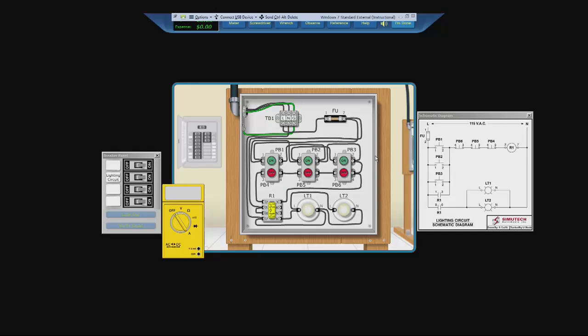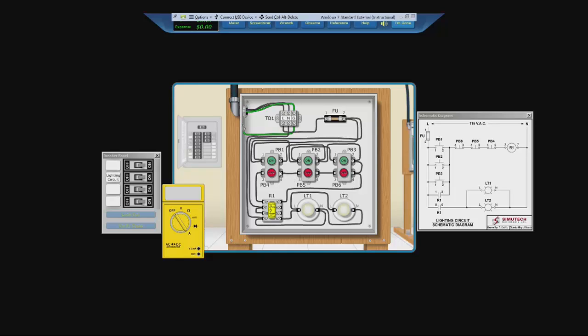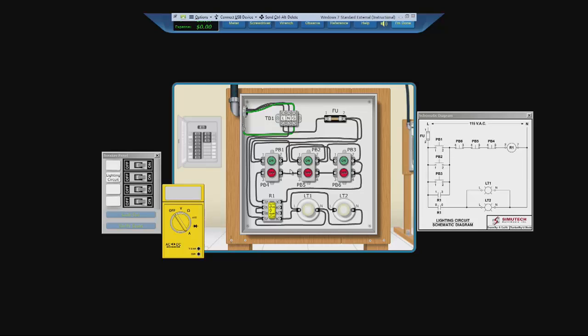By power of observation, we realized that we were getting power up to here, but we got no power at this end. Because of that, we knew the problem was someplace in between here and here. By using resistance, we were able to test whether we got a reading anywhere in here. By using voltage, we were able to determine that there was no power getting to this one, but there was to this. We found out that the wire was loose, and I've tightened it, and it now works. I hope this video is beneficial to you, and I hope that you get through the class well, and use the skills you learn in Simutech to apply to the rest of everything you do. Thank you.